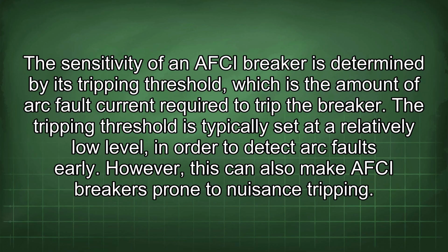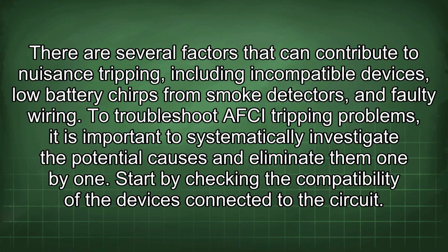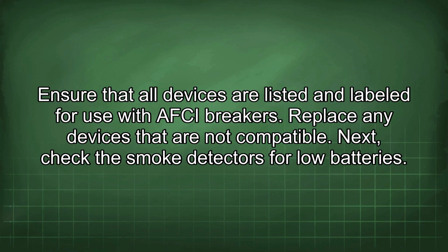Tripping threshold is typically set at a relatively low level in order to detect arc faults early. However, this can also make AFCI breakers prone to nuisance tripping. There are several factors that can contribute to nuisance tripping, including incompatible devices, low battery chirps from smoke detectors, and faulty wiring. To troubleshoot AFCI tripping problems, it is important to systematically investigate the potential causes and eliminate them one by one. Start by checking the compatibility of the devices connected to the circuit. Ensure that all devices are listed and labeled for use with AFCI breakers. Replace any devices that are not compatible.